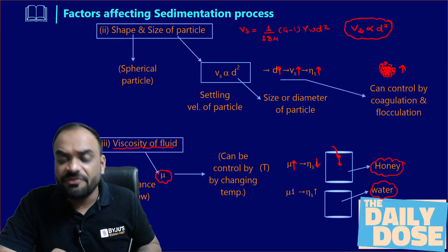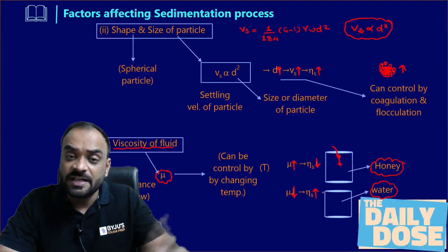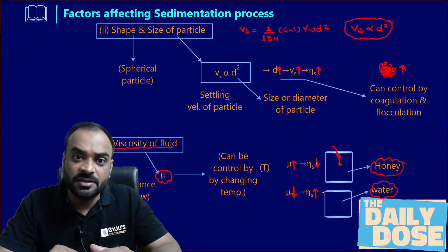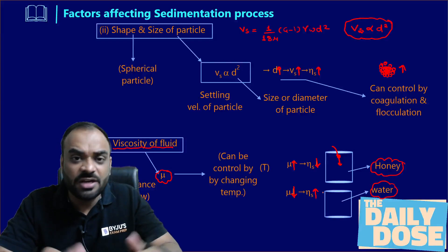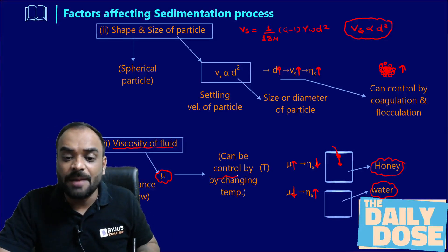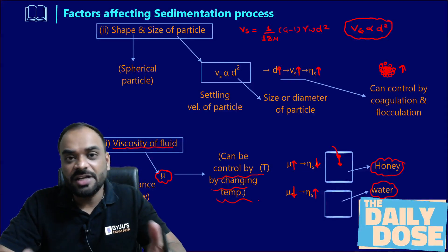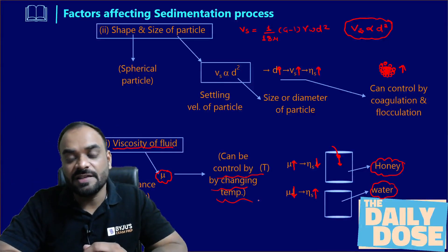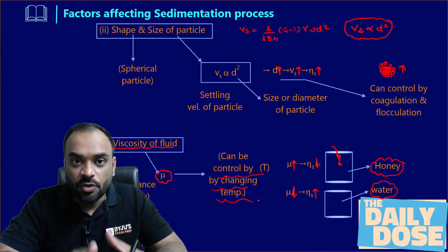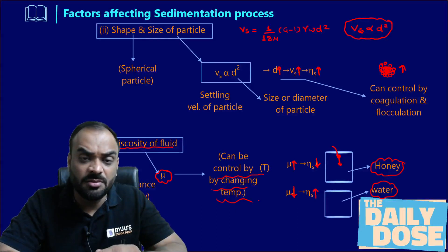In water, the dynamic viscosity is lesser, so the settling velocity will be higher compared to honey, and the sedimentation efficiency will also be high. Viscosity can also affect the sedimentation process. Now, can we control this factor? Yes — you can control dynamic viscosity by changing the temperature. However, the problem is that we are treating water in very large quantities to supply to the urban area, and it is not possible to change the temperature of such a large quantity. So we will not try to control temperature in our treatment plant. Therefore, only two of the three factors are practically controllable.